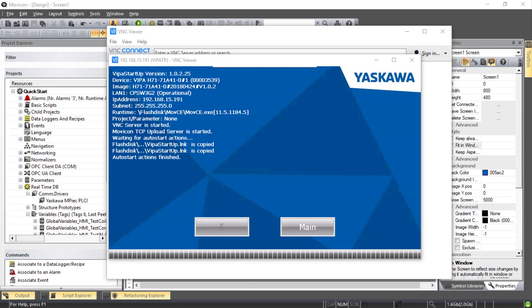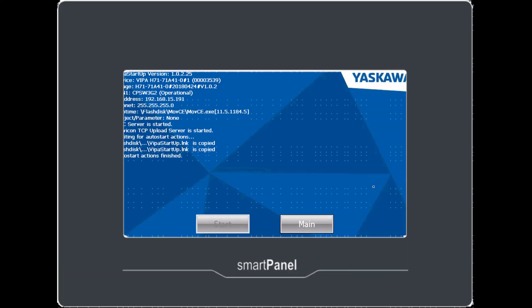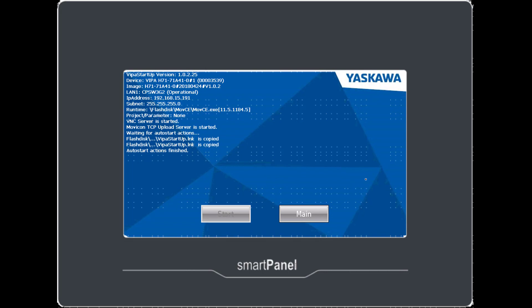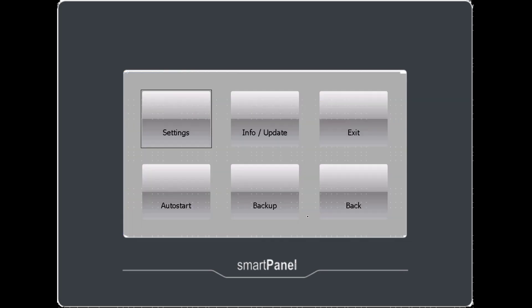I'm showing the Smart Panel screen through the VNC viewer. Power on the HMI. And when you see the blue boot screen with these two gray buttons, you want to press Main before the counter expires. Here in Main there are a number of things you can do. And the most important is to set a static IP address.